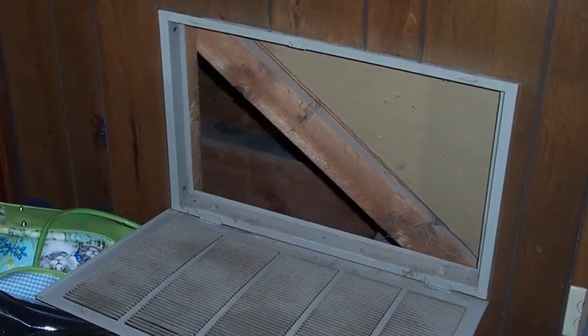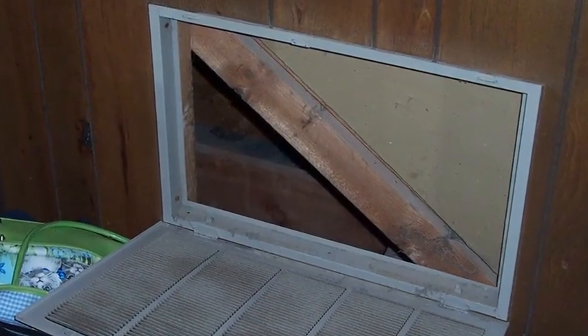What is a building cavity return? It's when hollow wall and floor cavities were used to carry return air. When you look into the return inlet opening, you see wood studs, wood joists, and the backside of drywall. This was simply never a good idea and is now banned in current building codes. They usually can be sealed significantly, if not perfectly, but it's complicated.